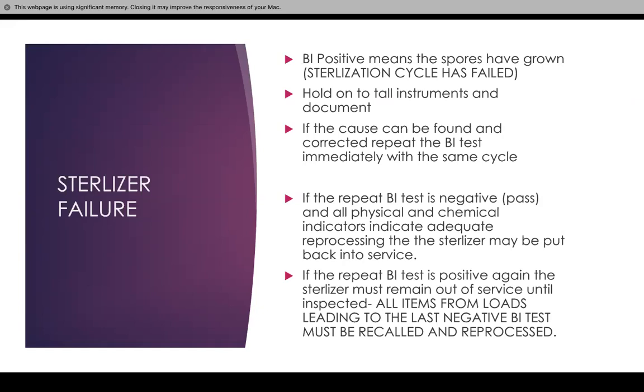If the repeat BI with the same cycle is positive again — there is a color change — the sterilizer must remain out of service until inspected. Every single item from the load, regardless of what it is, you have to recall it and reprocess it.